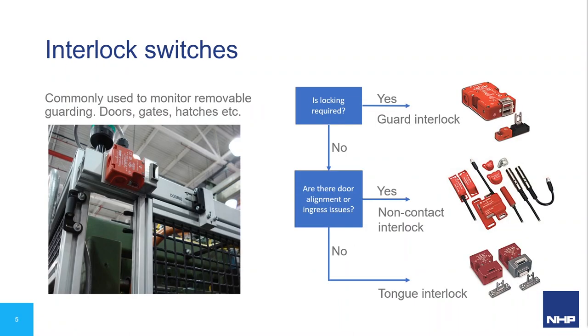Firstly, interlock switches. These are commonly used on removable guards on machinery to monitor whether the guard is in place. If the guard is removed or left open, the machine is not allowed to operate in a hazardous manner. As you can see from the image on the left, there's a typical installation with a tongue interlock switch monitoring a sliding guard. When the guard is closed, the actuator enters the switch and closes its contacts allowing the machine to operate. When the guard is slid open, the actuator is removed, the contacts open, and the machine turns off.